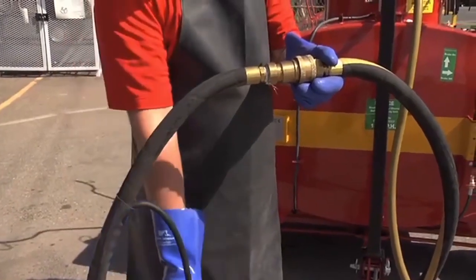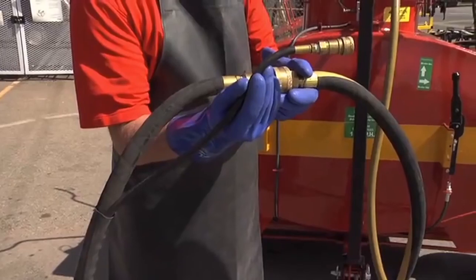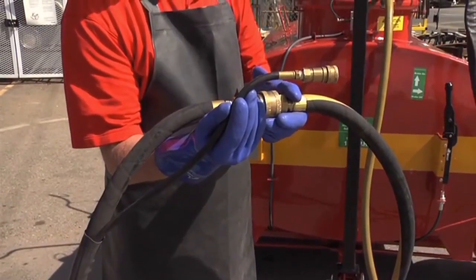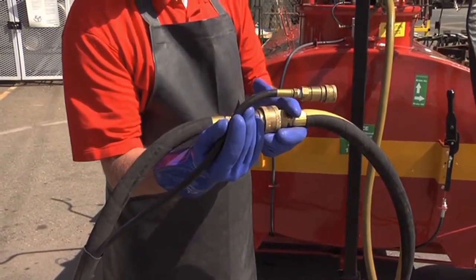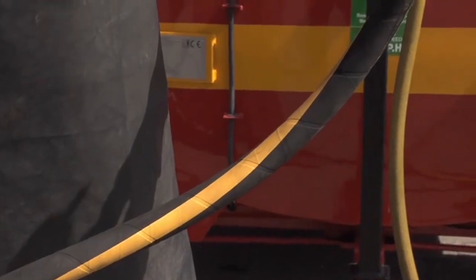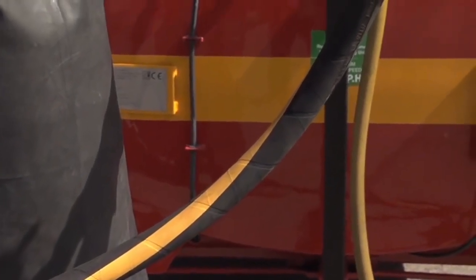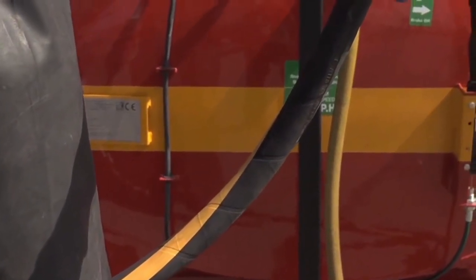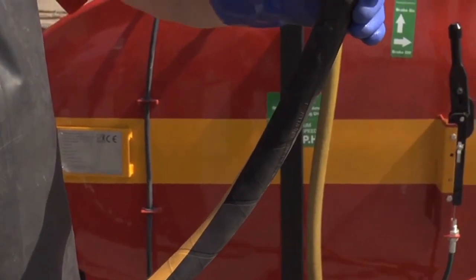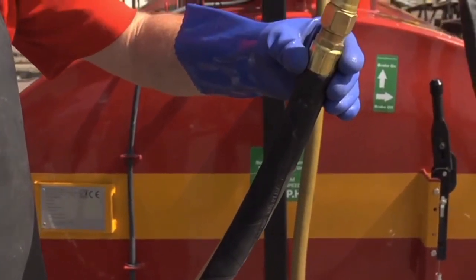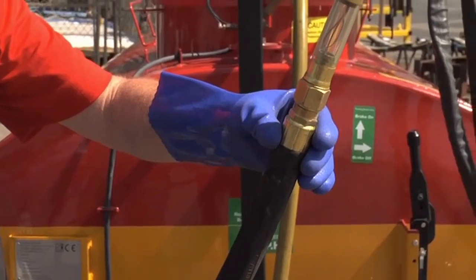Take a look at one of the duplex hoses. Inside the sleeve is the main fuel vacuum hose, along with the secondary vacuum hose that attaches to the drain tool. For safety, the main hose is carbon impregnated, which minimizes static buildup from flowing fuel and conducts any charge back to the grounded tank.